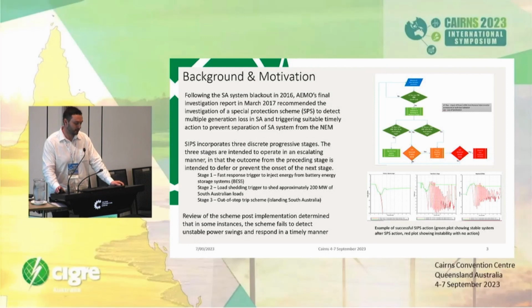Subsequent to this, some thought was put into developing a system integrity protection scheme, and you can see there the scheme itself incorporated 3 discrete progressive stages. The stages were intended to operate in an escalating manner, so that the outcome from the preceding stage was intended to defer or prevent the onset of the next stage. And this varied from triggering of BESS to load shedding to islanding the South Australian system.